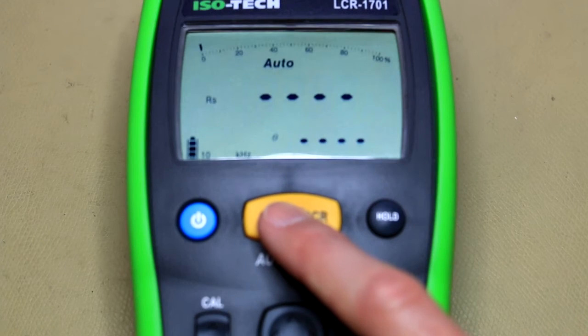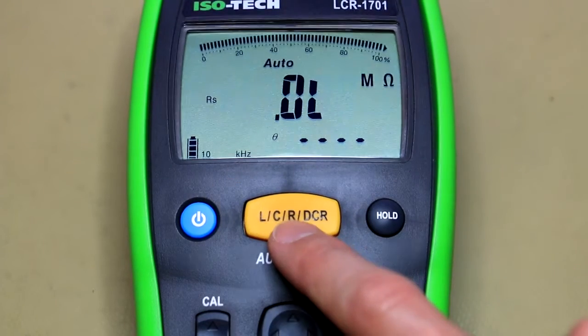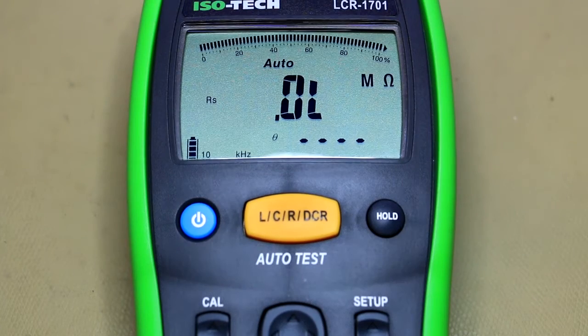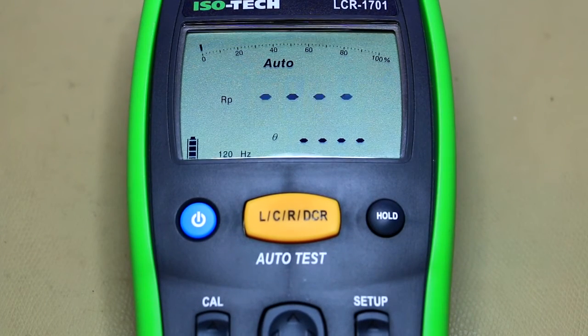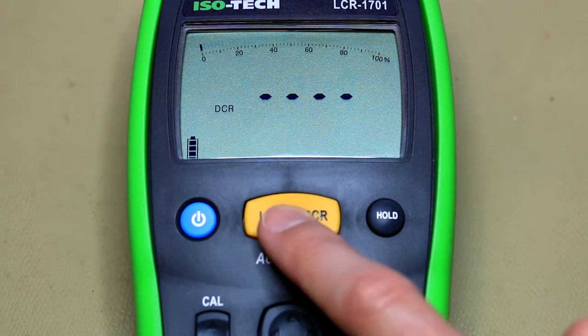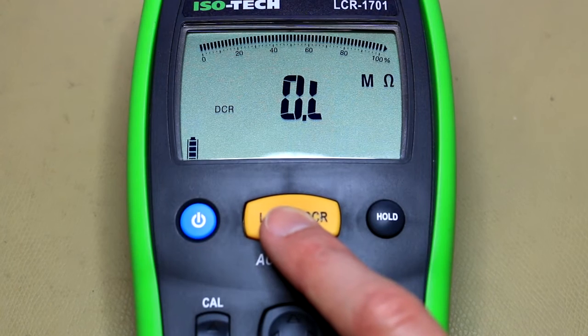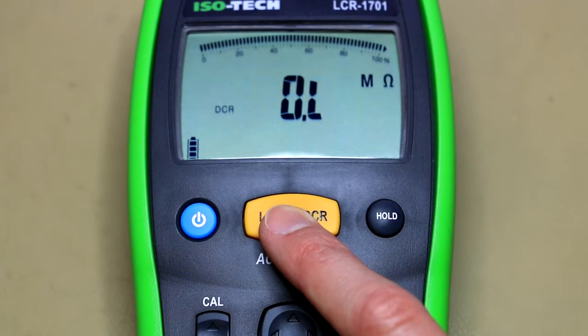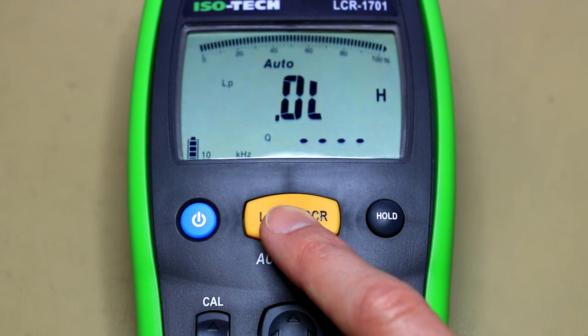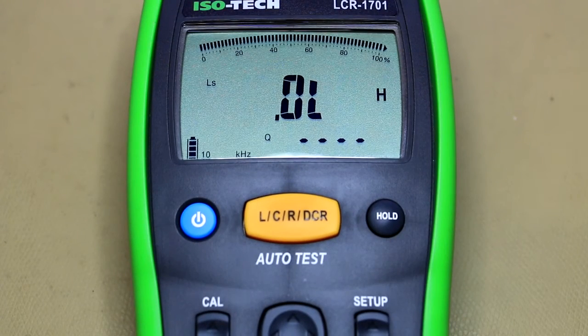Right, back to series mode. Next is just resistance mode at a specific frequency. Of course the frequency you can set to 10 kilohertz, 100 hertz, 120 hertz, 1 kilohertz, and back to 10 kilohertz. And then it's just got a plain old DC resistance mode for measuring standard resistors. It can go all the way up to 200 mega ohms. And there's the inductance mode, currently in parallel mode. Of course you can switch it to series mode, and you've got all the old suspects: Q, ESR, phase angle, D value, and so forth.